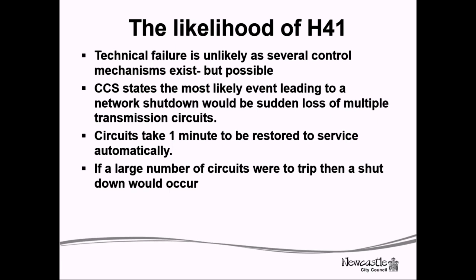We know in theory that if you get multiple loss of transmission circuits, you would have a system-wide trip. Circuits take 1 minute to be restored automatically. If a large enough number trip at the same time, you get a shutdown. Whether weather or a malicious threat could actually do that is another question.